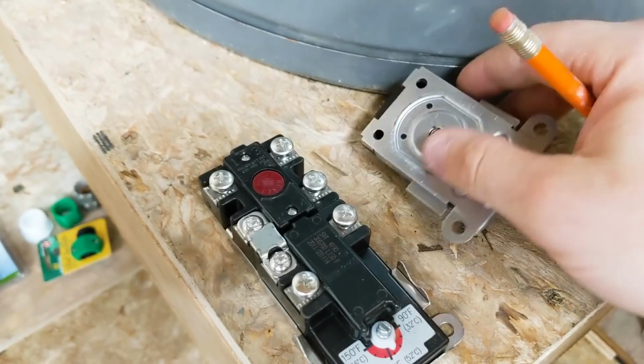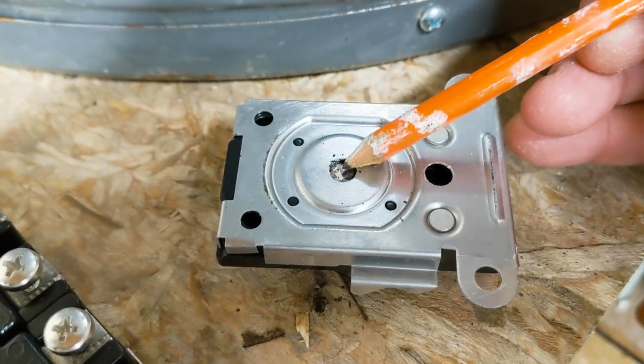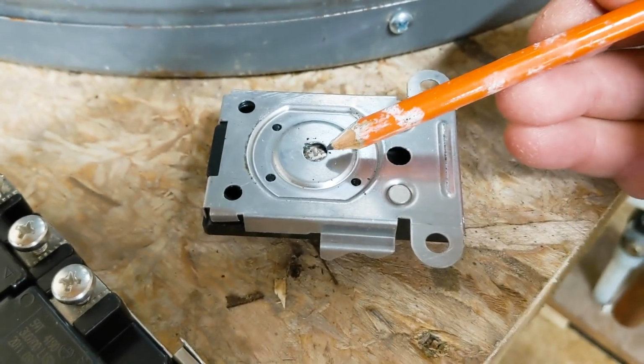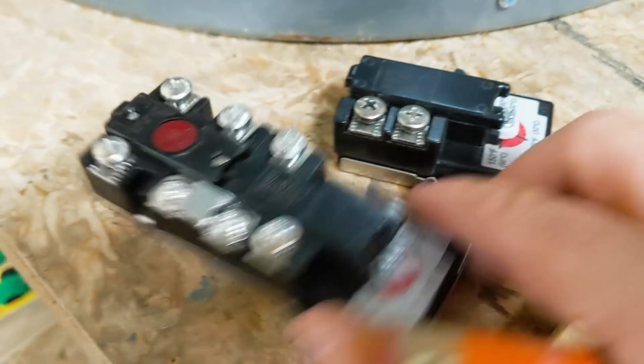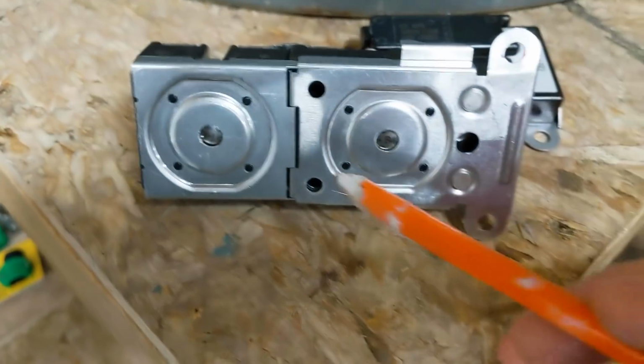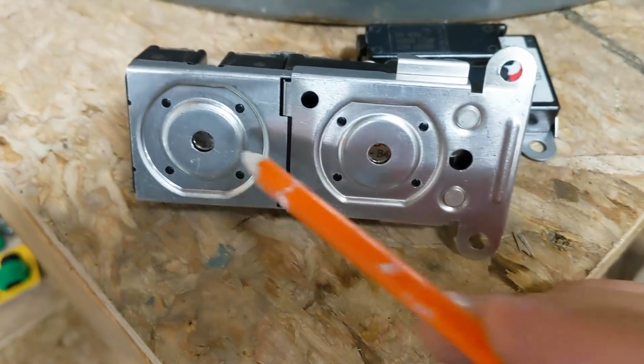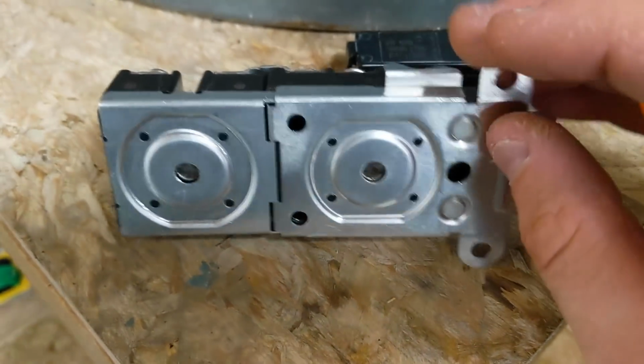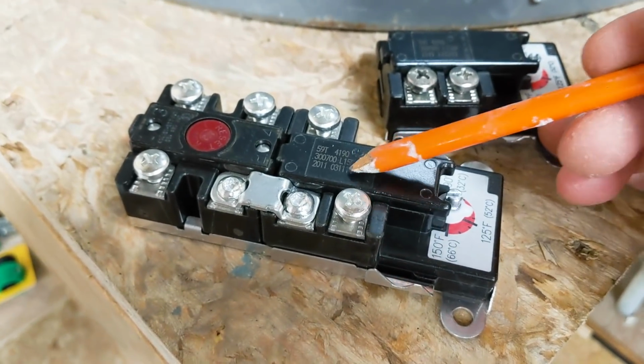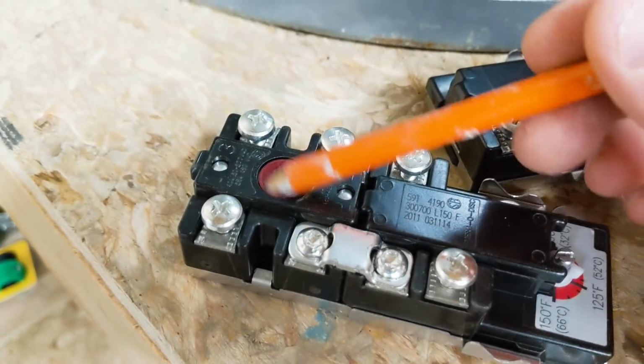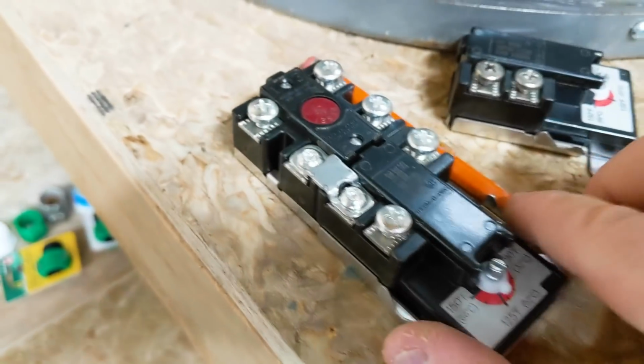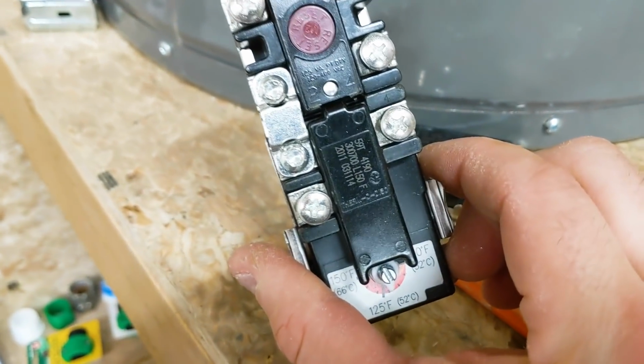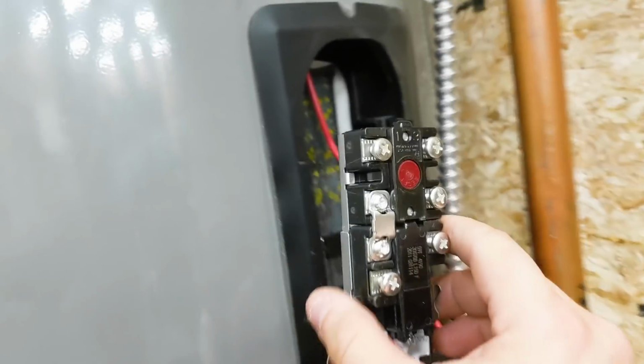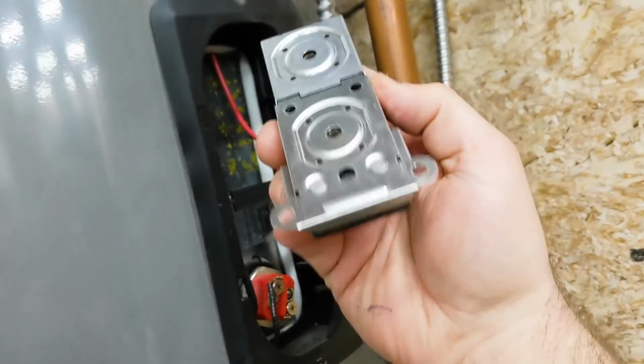So if we flip this over, this is the snap disc thermostat. So when the metal expands, it will snap open, and when it cools off, the metal will snap shut. And same here, except this one has two. So that's the thermal overload switch, and this one is the regular thermostat. So the thermostat just automatically goes in and out. This one needs to manually be reset. So it's exactly the same as up top. We'll just install this, and it should install the same way. So let's see. There's no glue or anything that gets put on these.